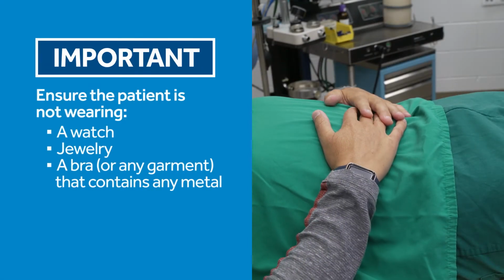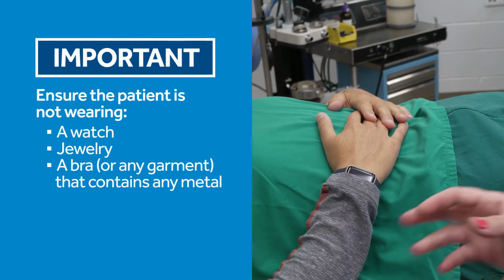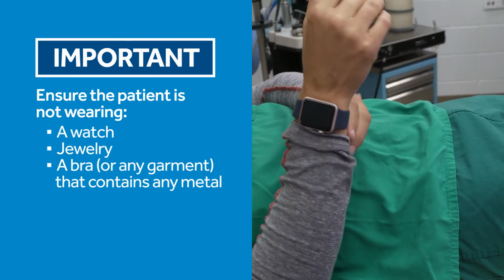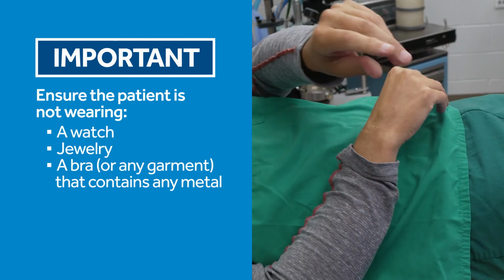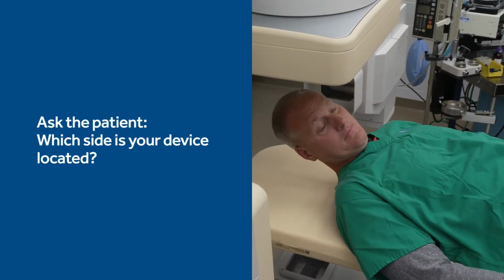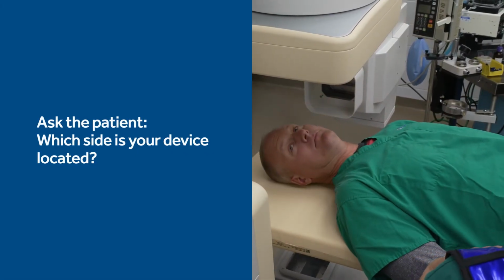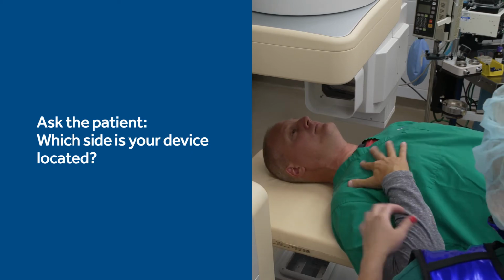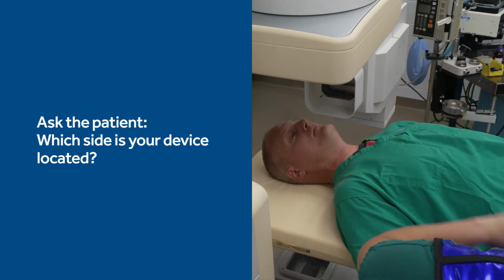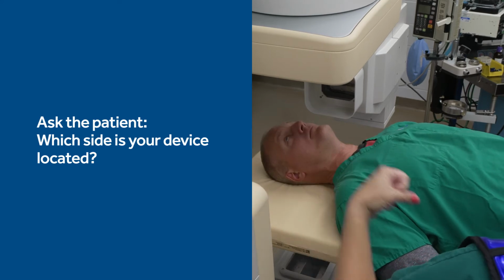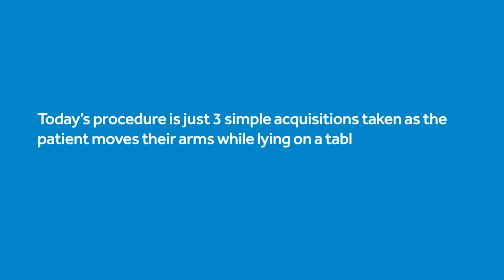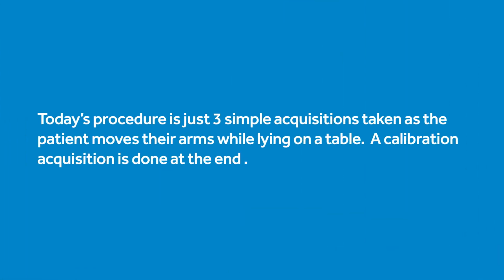Please confirm that the patient is not wearing a watch, jewelry, or a bra or any other garment that contains metal. Ask the patient which side of their body their cardiac device is located. All of the imagery you will be recording today will be focused on that device. During today's procedure, you will take the patient through a series of 3 specific acquisitions and capture imaging of the lead inside the patient's body as they do 2 arm movements and 1 static image set.